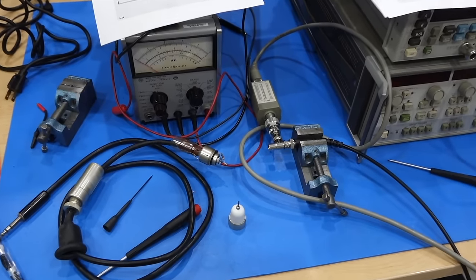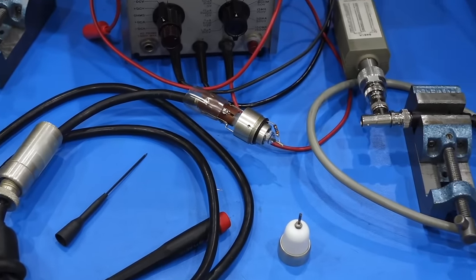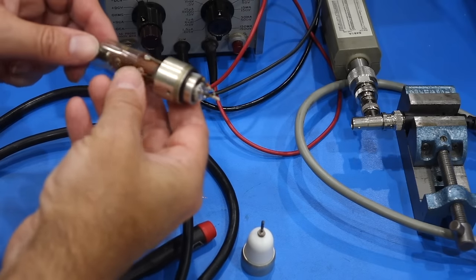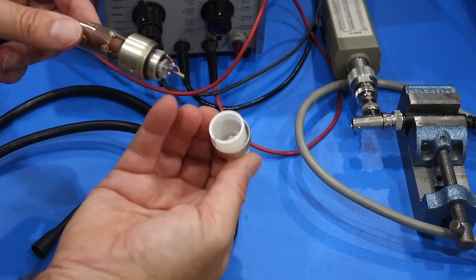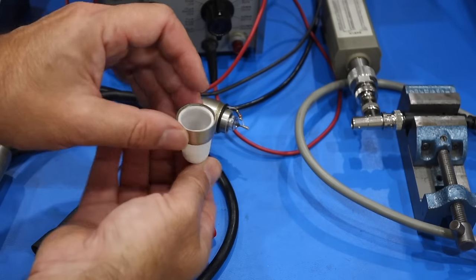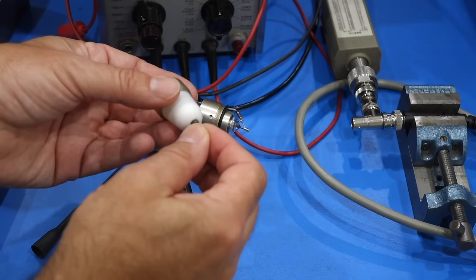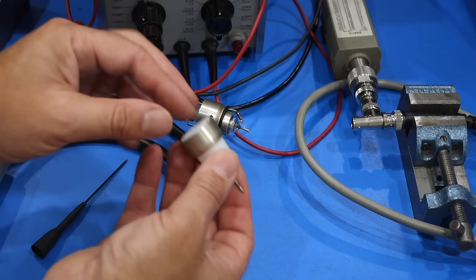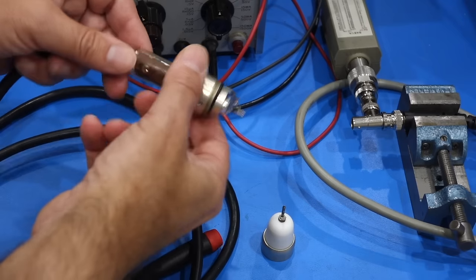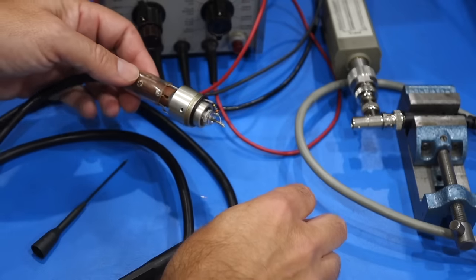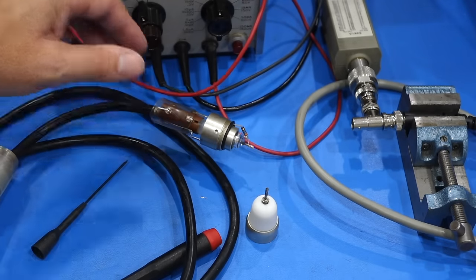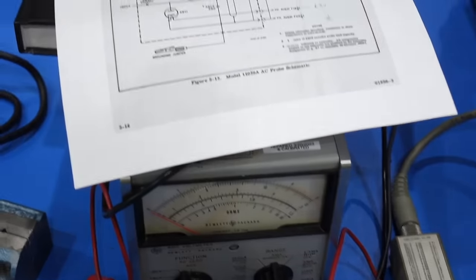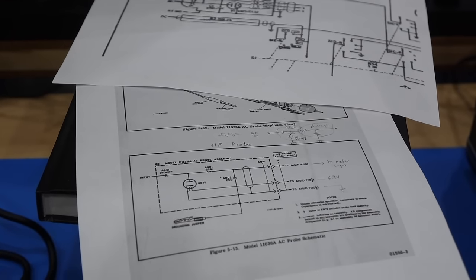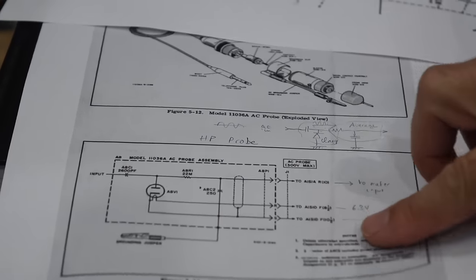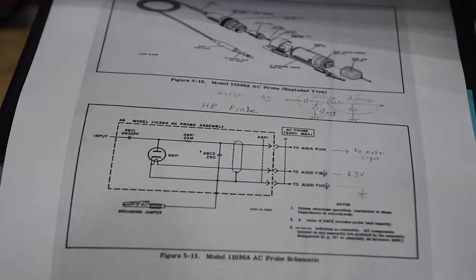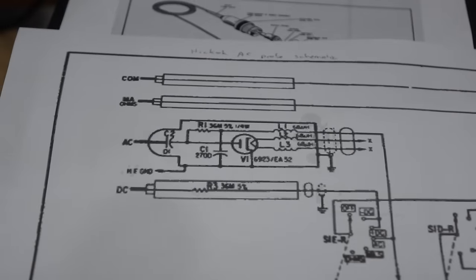So I was trying to figure out what the difference is between the HP probe and this Hickok probe. And that's the deconstructed Hickok probe. And so the way it works, there's actually a capacitor in here after the probe that's embedded into here, and then it goes into the valve, and there's a little circuit and that screws up on top. And we already knew that the resistance is wrong, but except from that, the two probes are very similar. That is the HP probe, and that is the Hickok probe.